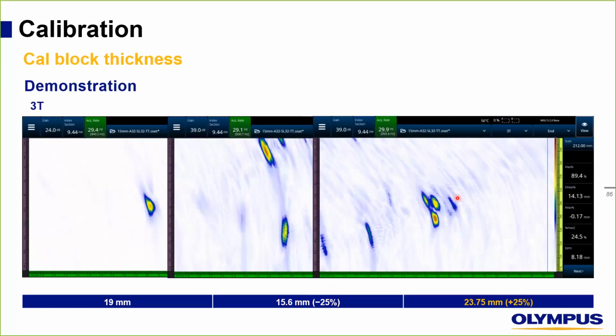If ever you have just one thickness for the calibration block and you need to inspect a different part thickness, my recommendation is to use the same calibration block thickness as the part you inspect.